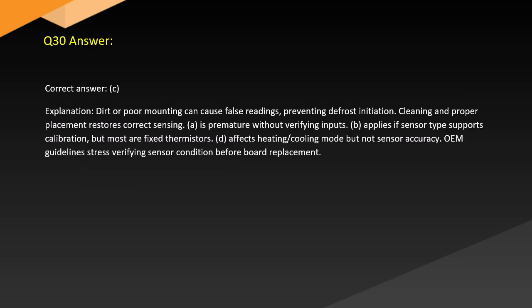Answer. Correct answer: C. Explanation. Dirt or poor mounting can cause false readings, preventing defrost initiation. Cleaning and proper placement restores correct sensing. A is premature without verifying inputs. B applies if the sensor type supports calibration, but most are fixed thermistors. D affects heating and cooling mode, but not sensor accuracy. OEM guidelines stress verifying sensor condition before board replacement.